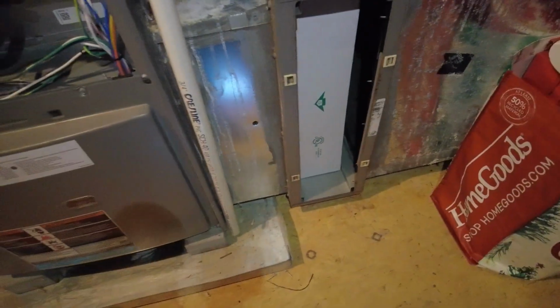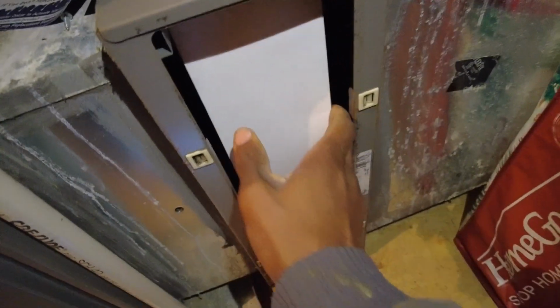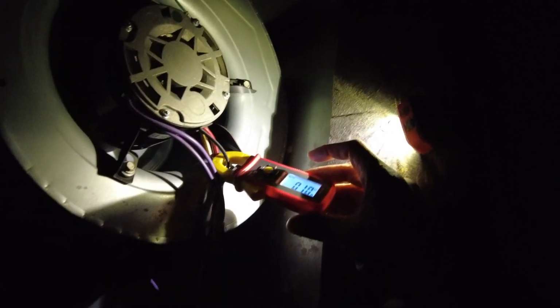What I'm going to do as well, I'm going to go ahead and verify the blower speed on this thing simply by, once again, grabbing my little meter here, and I'm just going to grab one of these speed taps if possible. Should be able to reach it, but we might not be able to take you along with us. So let's see here. I'm going to grab black first. It's my first guess. Turn the light on there. Aha, nothing on black. So I knew we weren't running high speed. It's just too quiet. And we have a high temperature split. We have a 22 degree temp split.